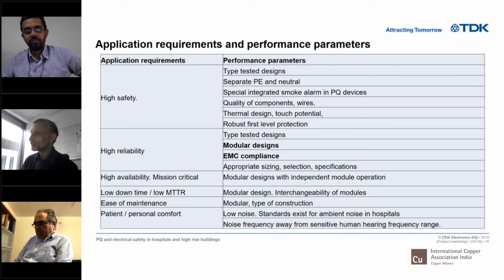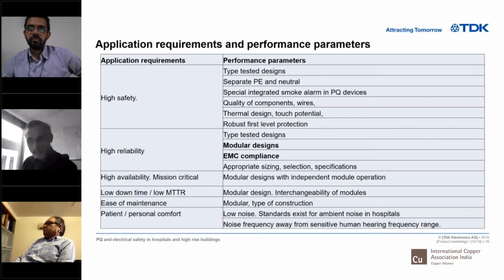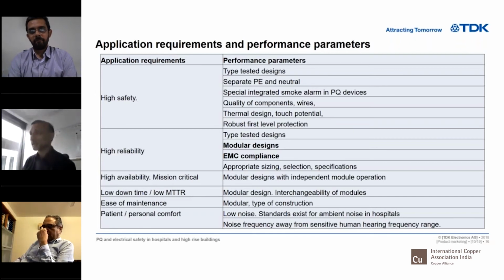Then the quality of components and wires; the most important is the thermal design and the touch potential. Because of the lack of time, I didn't get into how, with neutral shift, people can even touch the surface of a panel or a so-called dead design, but get electrocuted because of neutral currents and leakage currents. Leakage current is one of the biggest killers if the leakage current design is not properly taken care of. And a very robust first level protection. That means you have a fire alarm, you have a firefighting system, but the electrical equipment, be it the Buchholz relay or the overcurrent relay or the earth fault relay, is the first line of defense and should have a very high level of reliability.